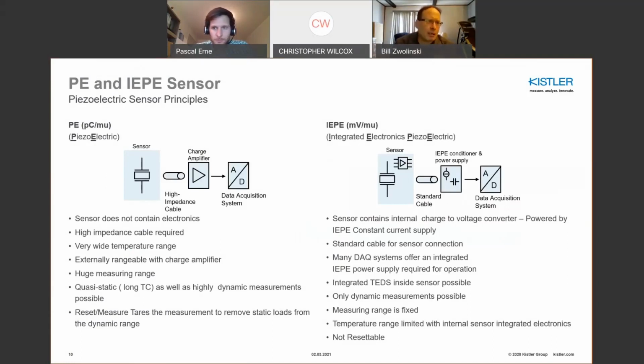Some terminology: piezoelectric and IEPE sensors. Basically, piezoelectric sensors do not have any electronics inside, and they rely upon an external charge amplifier. What this does is the external charge amplifier is very capable to range the measuring chain for whatever measuring ranges are of interest. And so this allows you to optimize the dynamic range of the measuring chain to the actual application because of the flexibility of rangeability. Also, when it comes to instrumenting your platform with force sensors, there's a preload operation which requires a quasi-static operation. Well, piezoelectric sensors with a quasi-static charge amp allow measuring of these static or low frequency forces to make sure that it's properly preloaded. We're going to talk a fair amount about preload as we go forward.